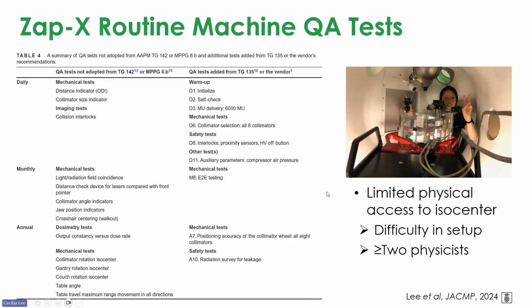But the biggest challenge of performing QA was that we have limited physical access to the isocenter. The machine is all closed, and once the table goes in, the isocenter is inside. A lot of times physicists retract the table outside the unit, set up the phantom, and send it into the isocenter. The majority of the time you can do that, but certain tests you cannot do.